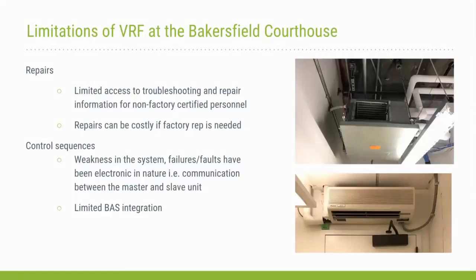Weaknesses in the system have been electronic in nature. So again, we kind of get into a black box area where it's not traditional refrigerant and electromechanical components that we're experiencing trouble with. In that sense, the units have been very reliable and relatively trouble-free. The experiences that we've had have been faults in serial communications between the master and the slave unit, and it really drives us into a corner where we are almost forced to rely on the manufacturer to provide us that technical support. Again, limited BAS integration.